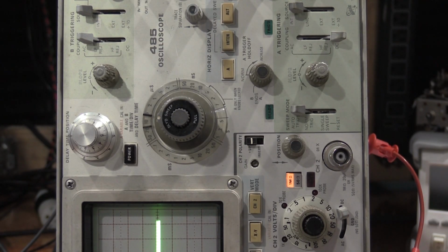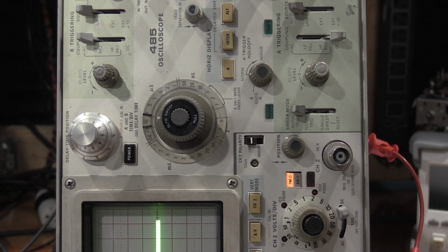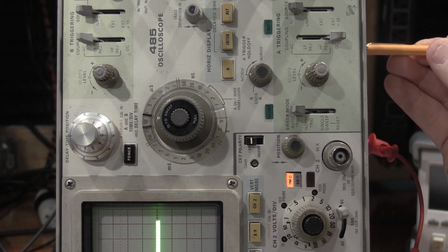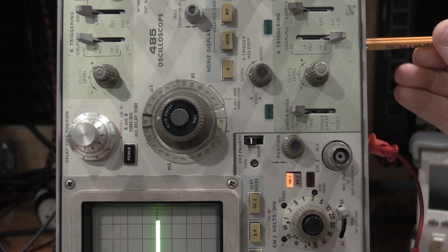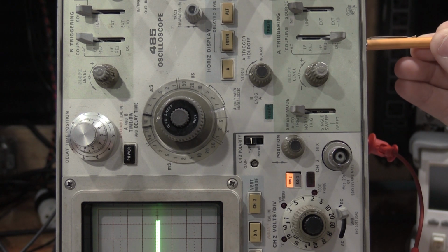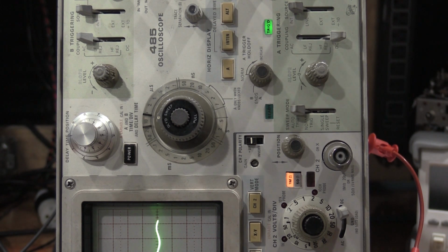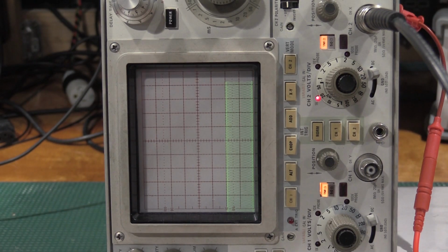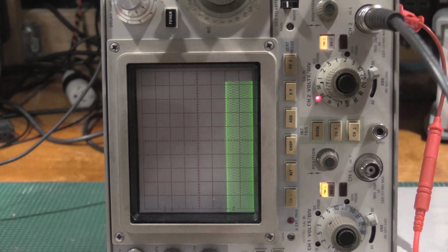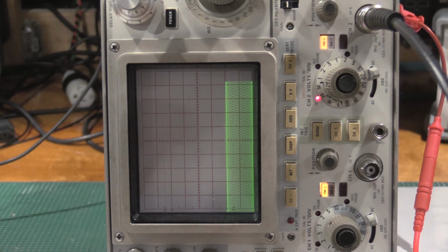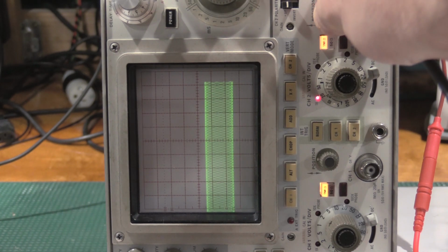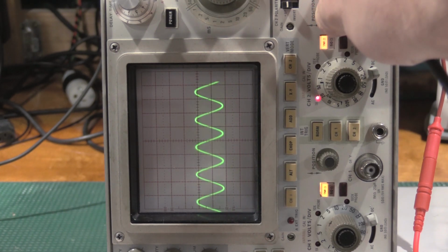Sorry, I need to redo the level centering because I forgot to switch to DC. That's going to be a problem. It caused a slight adjustment, not much. Before we do the external trigger, we need to check channel 2. So I moved the signal to channel 2, and we want to check that triggering happens within 0.5 divisions of graticule center. And it does.